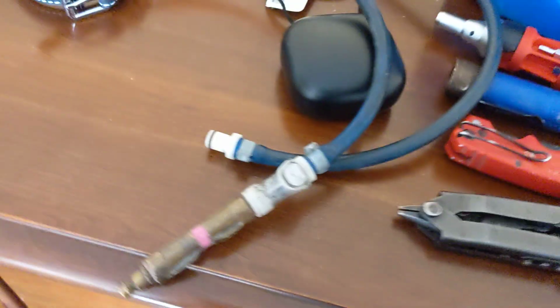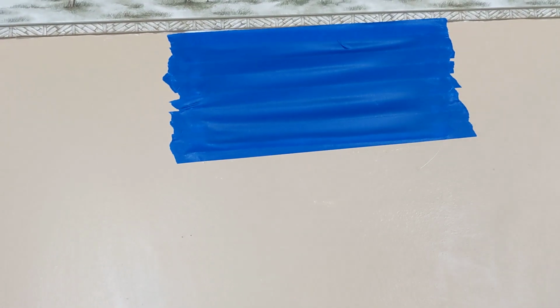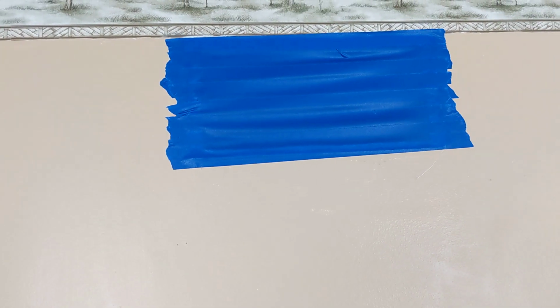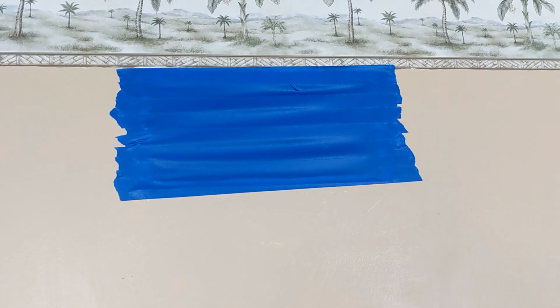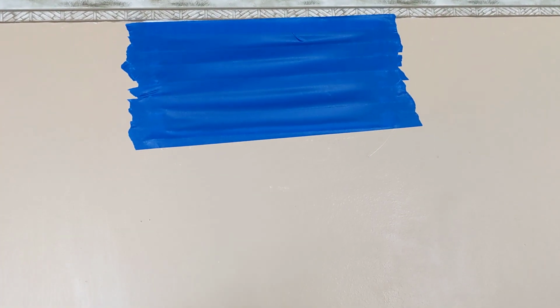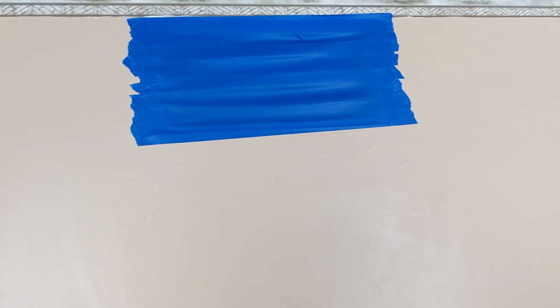And there's a lot of different types of whip tips. So for instance, this whip tip right here plugs into the end of that hose, and then compressed air goes through here and it whips it all around inside the ductwork. So that way not only is compressed air coming out of the hose blowing all the dust and dirt and debris through the ductwork down towards the collector that's hooked up downstairs that we looked at in the laundry room, that's pulling all the dust and dirt and debris through that way. So we're pushing everything through one direction as the HEPA collector is pulling it all through the other direction.